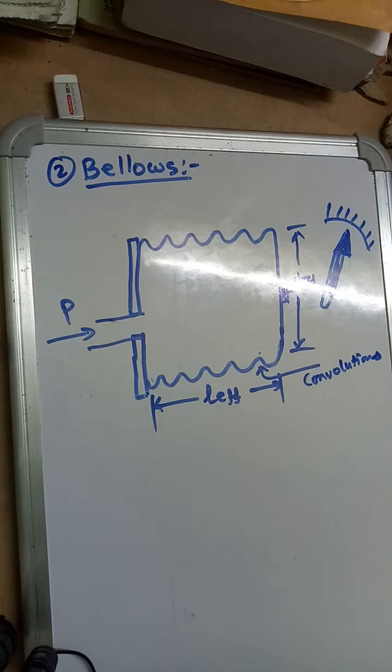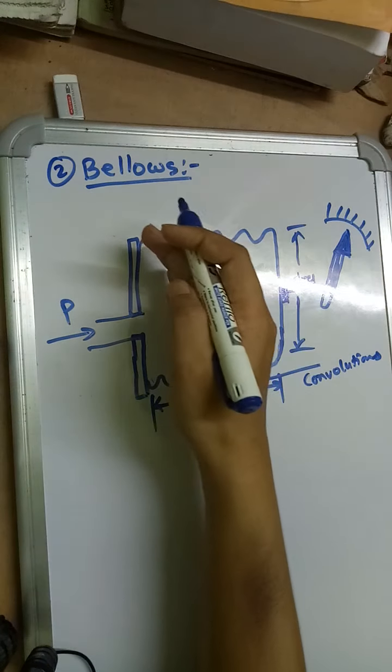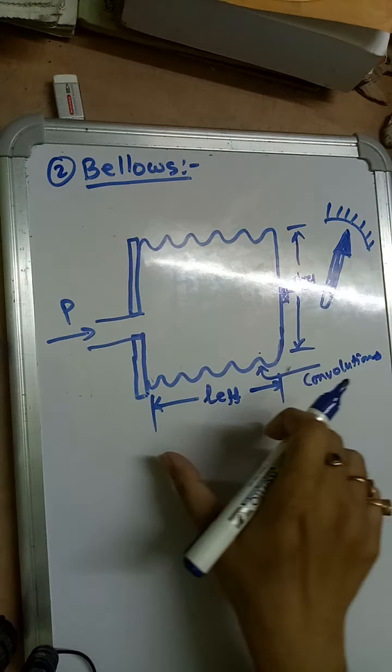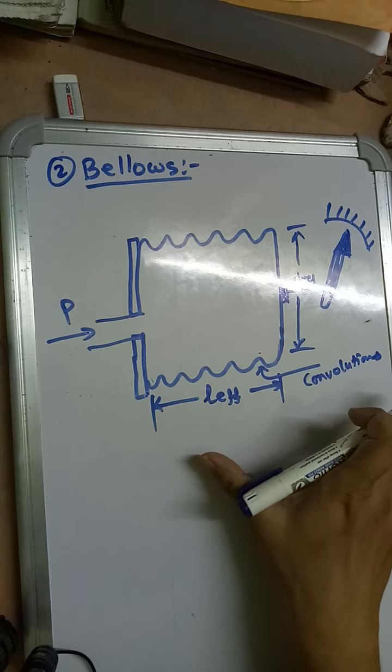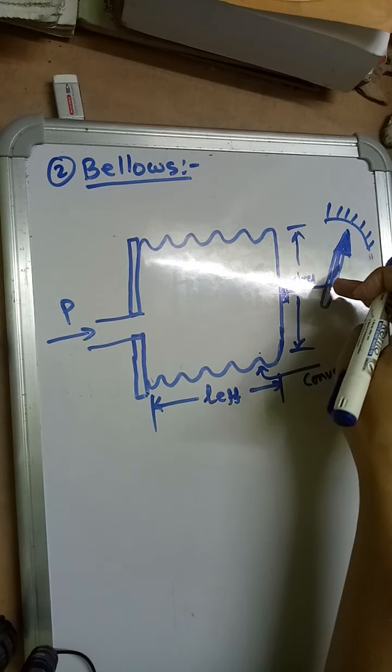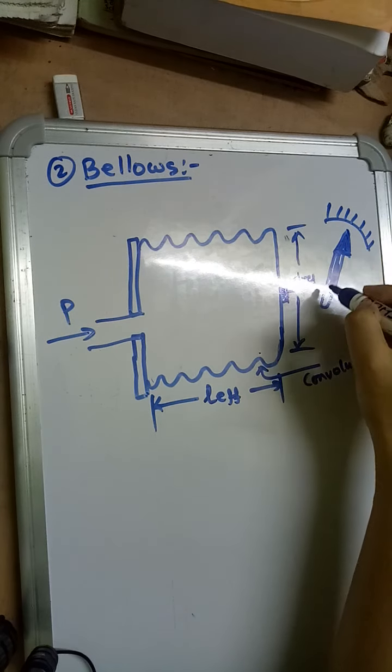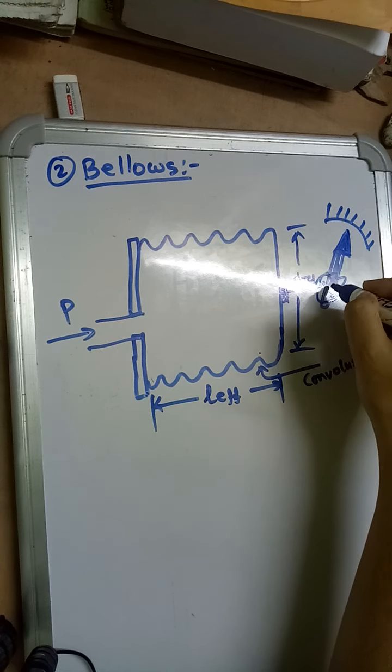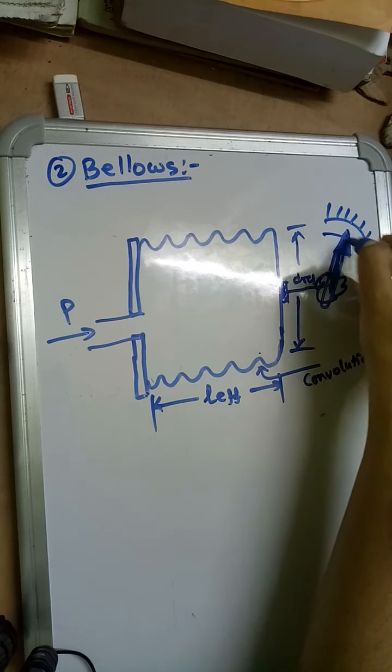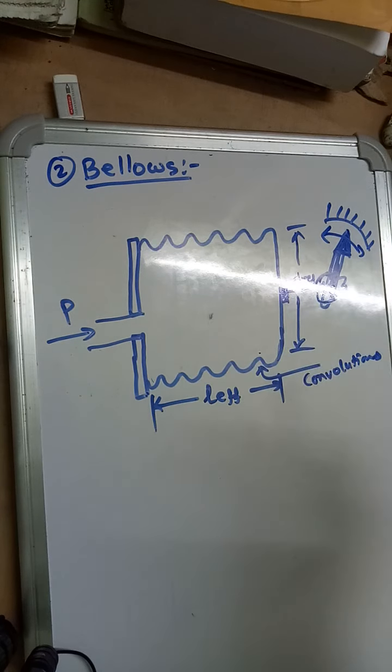When the pressure is applied, these convolutions will expand and this L E double F will expand. As it expands, this gear will move. Some gear technique will be there. Due to this, the pointer will move in these directions and mechanical output will be obtained. How to convert it to electrical form I will discuss later.